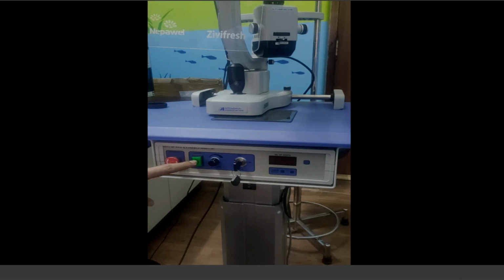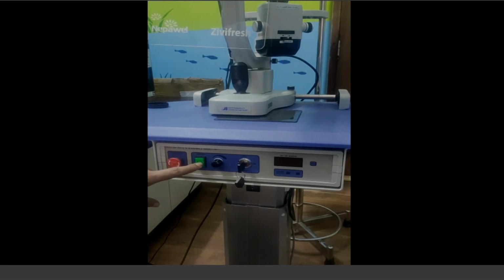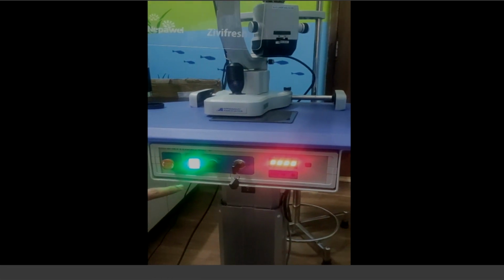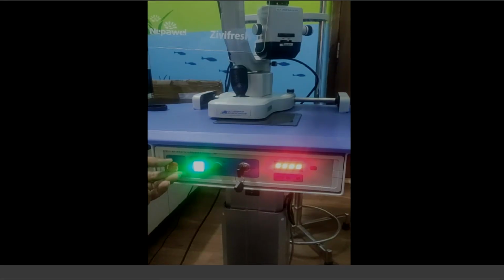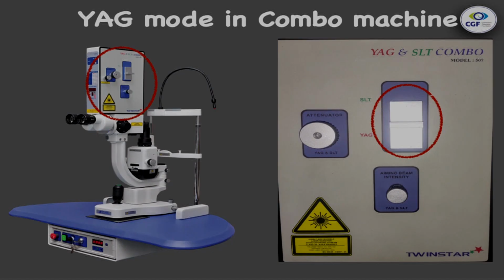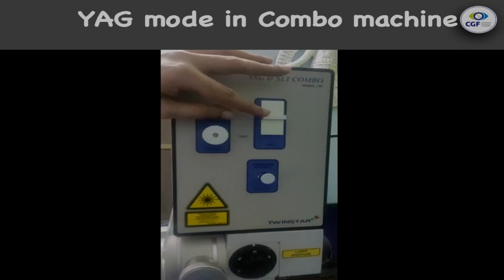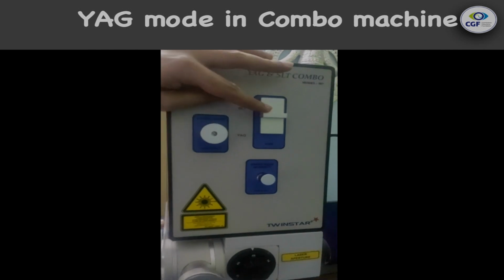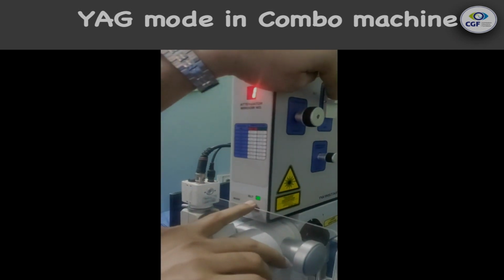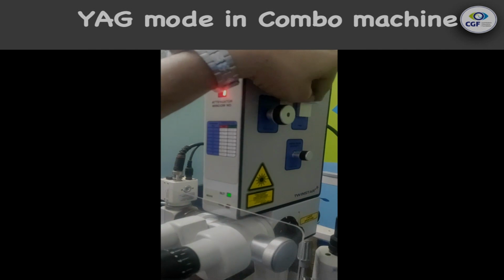One is the SLT combined Appasamy YAG laser machine. One is without SLT. So there are two different machines. So make sure that SLT mode is switched off and you go with only the YAG mode. So that is the first step. And the second step is, this is the SLT mode, and then switch to YAG mode.